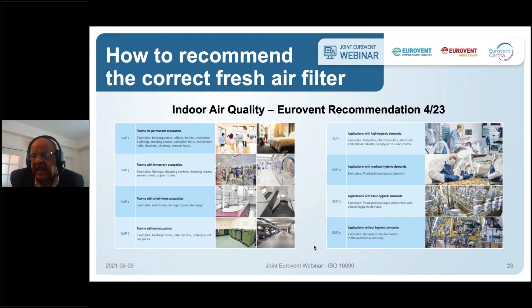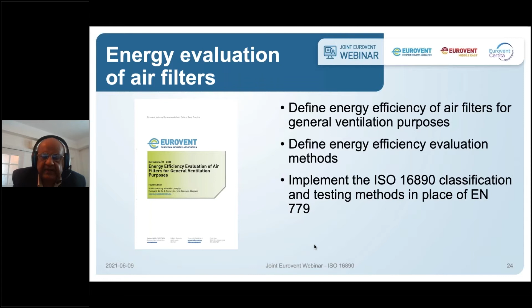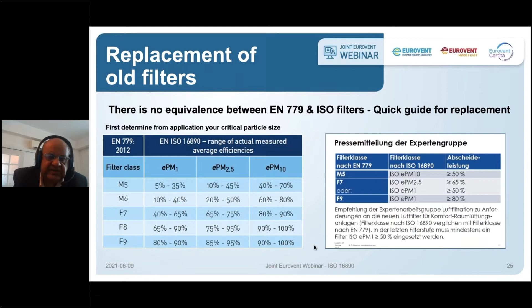So you will hear, and this document, as Marcus said, is available. Go through the detail, it's a very important document for HVAC engineers. Some service people will also be joining in, and they're used to this nomenclature, the F7, F8, F9s, and how they would go ahead with replacement of filters. This has also been provided in guide documents, and a lot of other systems have written about it, so you would not fall short as far as replacement filters are concerned. I understand Mark is going to take this further into one-stage and two-stage filtration, and how you would put in your first stage and second stage.